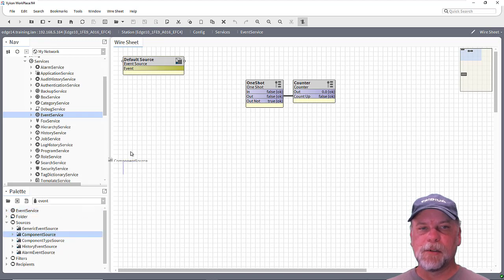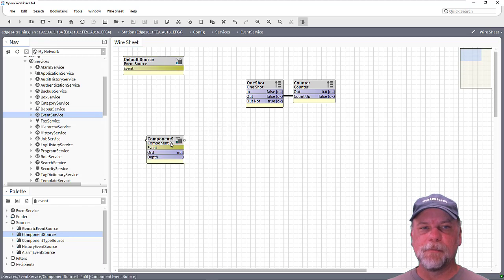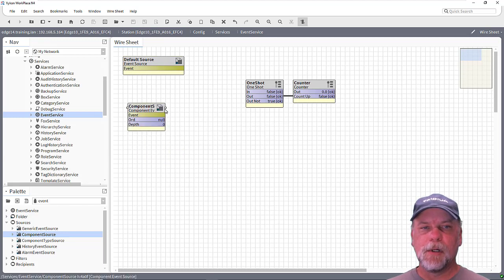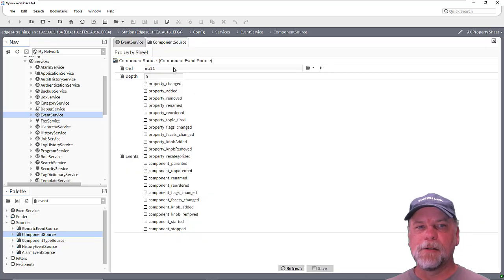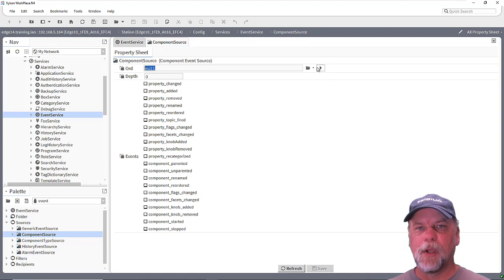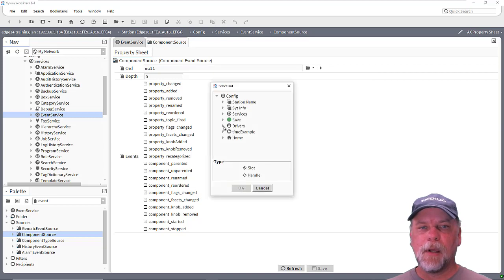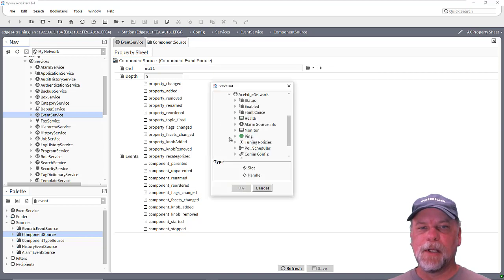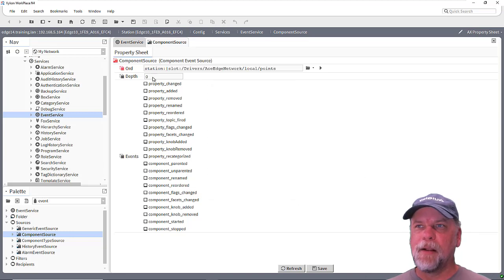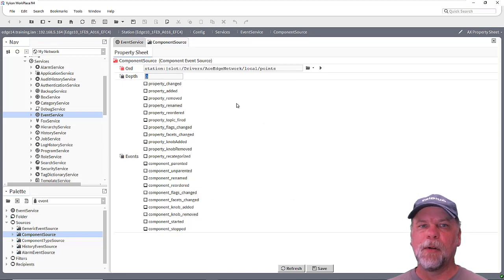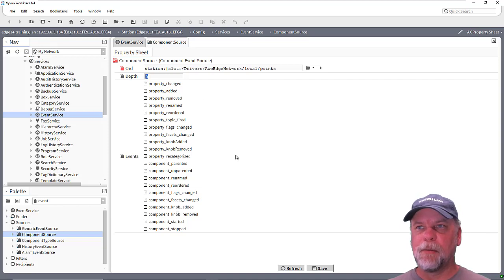To give you an idea how this works, I'll drag in a component source here and go look at the property sheet. There's an ORD property here, which says where in the station should this source monitor for component events from. So I'll use the component chooser and pick the drivers and the ACE Edge network, go into the local device, and select the points container. And then there's a depth which means how many children deep.